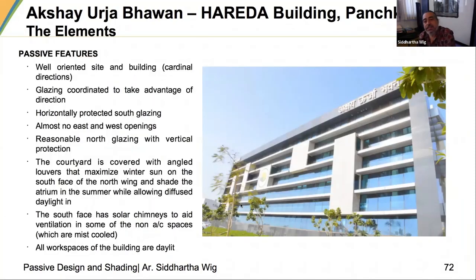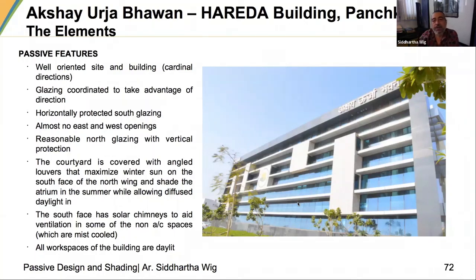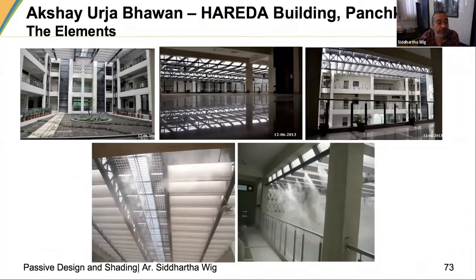Looking at the passive features: the orientation of the building, the glazing, the chajas and shades — designed for maintenance as well as to allow winter sun in while cutting summer sun off. There were almost no east or west openings. We used a reflective tile with a very high SRI on the roof, achieving a net temperature drop of nearly 13 to 15 degrees Celsius.